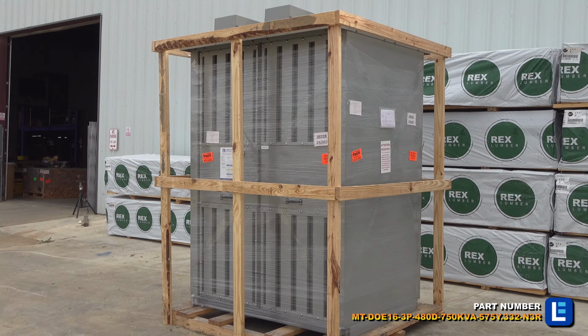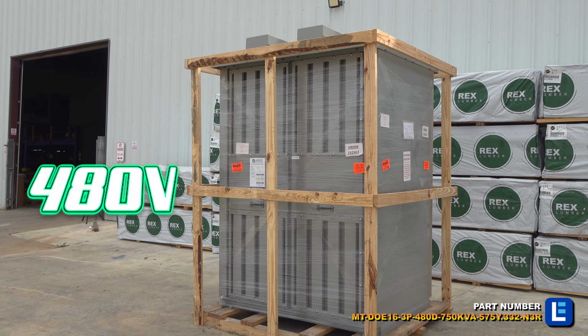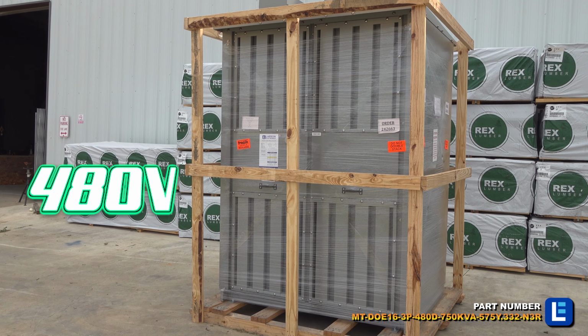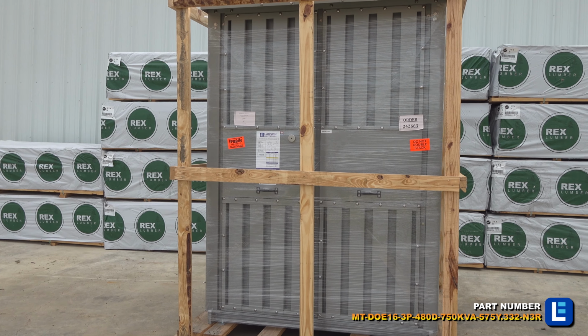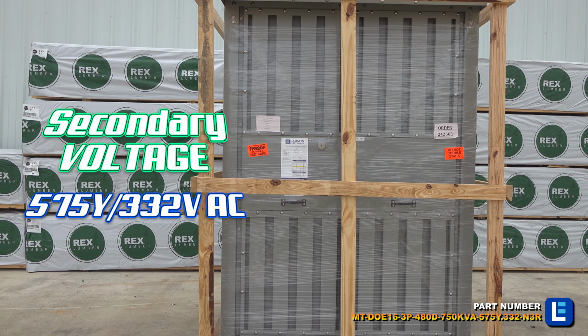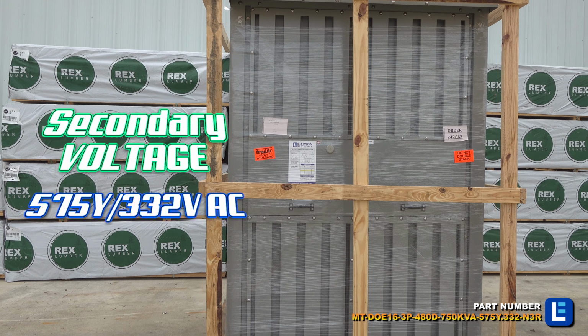This isolation transformer is configured with an input voltage of 480 volt delta three-phase AC on the primary side and an output voltage of 575 Y 332 Y neutral three-phase AC on the secondary side.